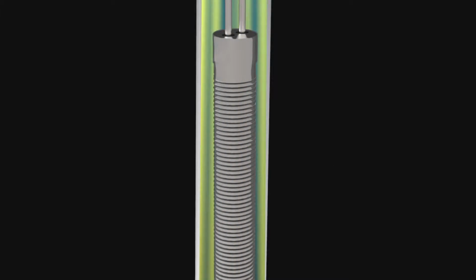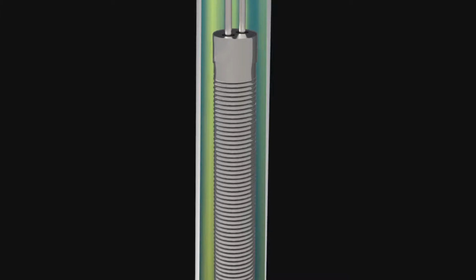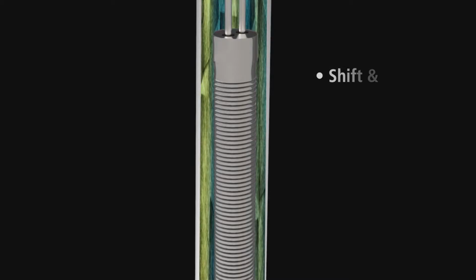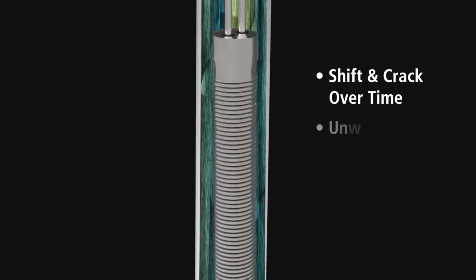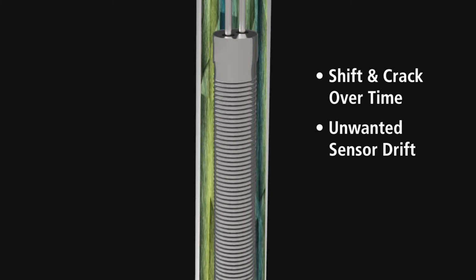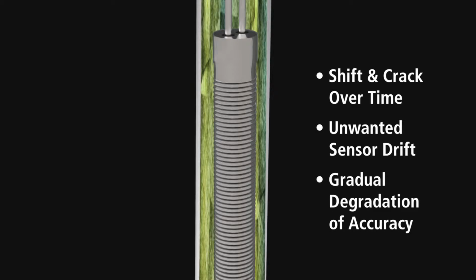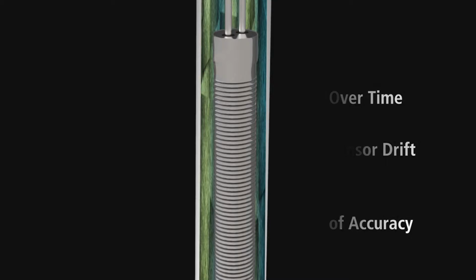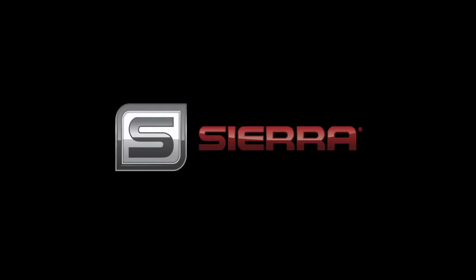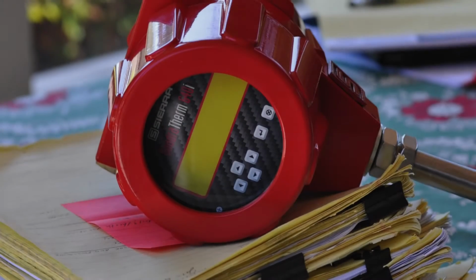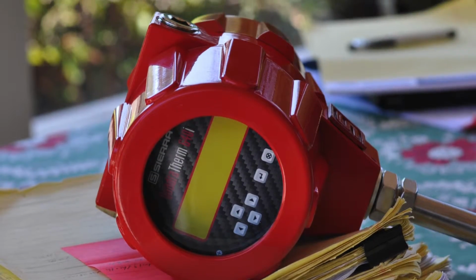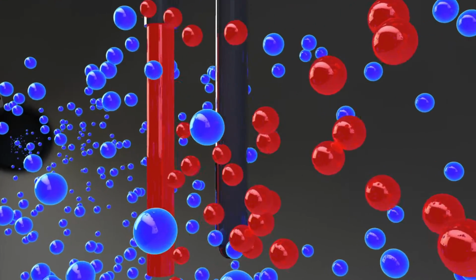Wet thermal sensor design, because of the organic potting cement used, would shift and crack over time, causing unwanted sensor drift, resulting in a gradual degradation of flow measurement accuracy. Today, wet thermal sensors are used by all industrial thermal sensor manufacturers on the market, with one exception, and that is Sierra. Sierra never stopped improving the technology, knowing that wet sensor drift problems must be solved.